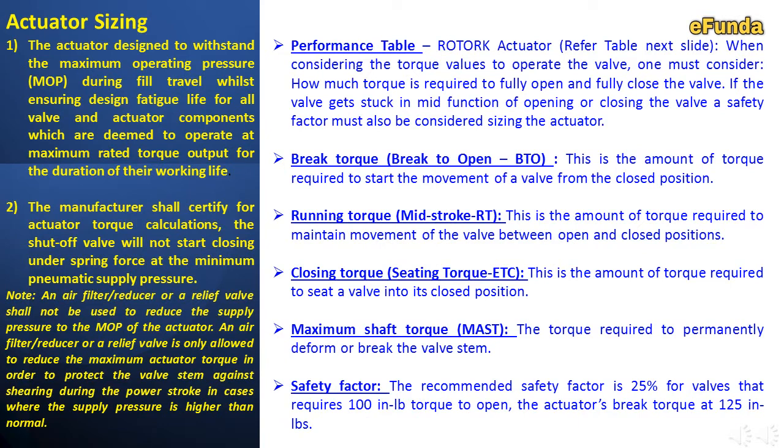Some of the key terminologies are required to be understood. Break torque, that is break to open, abbreviated as BTO. This is the amount of torque required to start the movement of the valve from the closed position. The second one, running torque, that is mid stroke, that is RT.